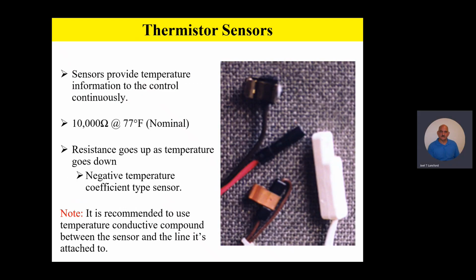The first thing that we'd like to talk a little bit about are the sensors themselves. The sensors are going to provide temperature information to the control board continuously. Now, let me stress this. Throughout the year, it doesn't matter if it's summer, winter or fall, the sensors are going to be reading outdoor air temperature as well as coil temperature.